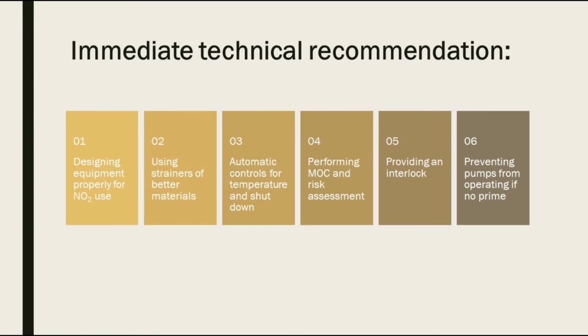Here's a list of immediate technical recommendations, some of which are from the safety standard that was developed in part by AirGas, CGA G8.3. Number 1. Designing equipment properly for N2O use. Number 2. Using strainers of better materials such as high nickel or copper alloys. Number 3. Automatic controls for temperature and shutdown. Number 4. Performing management of change and risk assessment whenever critical equipment is being changed. Number 5. Providing a safety interlock to ensure proper liquid filling and pump cooling before pump can start. Number 6. Preventing pumps from operating if they lose prime.